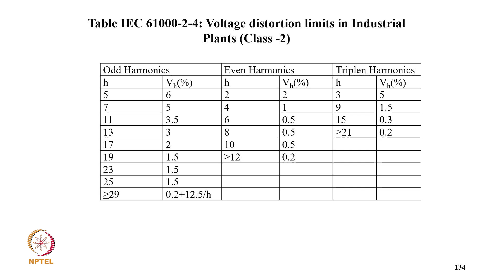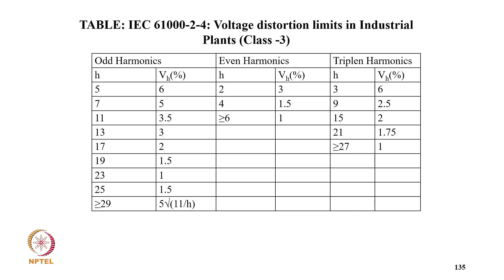And this is typically the voltage distortion for class 2 industrial systems, with the odd harmonics, even harmonics, and triplen harmonics limits. This is typically the class 3 voltage distortion limit in industrial plants, again given for odd, even, and triplen harmonics. Now coming to power quality monitoring, that becomes important: first you have to monitor the power quality, then you can say power quality is not good, or that you have to limit it.